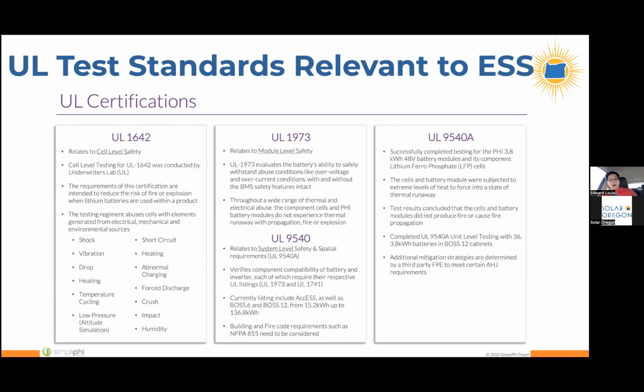So in the world of hundreds of UL certifications and standards, the ones that are relevant to batteries are the following. UL 1642 defines a series of tests to test the individual battery cell against shock and vibration. Of the long list of tests, the more interesting ones are the short circuit test, where you take a battery cell and just dead short it and see what happens. Some cell chemistries will explode in a very dramatic fashion. Others, when you short circuit them, do very little. It's very anticlimactic. And then there's also abnormal charging. So if the battery management system goes berserk and overcharges the battery, what will happen? That's another test.